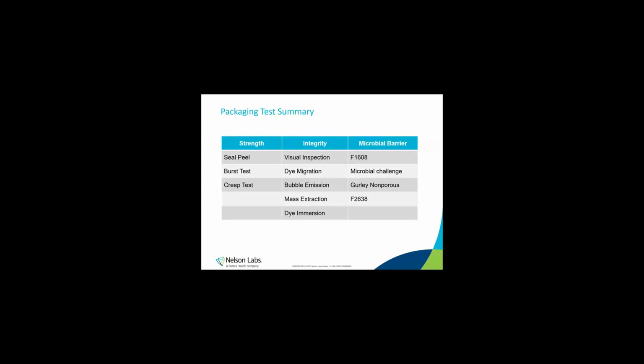ISO 11607 has a very long list of tests that can be used to evaluate many properties, and if none of those listed options appeal to you, then they allow you to create a custom method as long as it's validated. Nelson Labs offers the most common tests used in industry in each of these 3 categories. This table shows our offerings for strength, integrity, and microbial barrier tests. Each of these methods has pros and cons, and some are preferred over others in certain situations. For a packaging validation, you would select at least one test from each of the 3 columns.